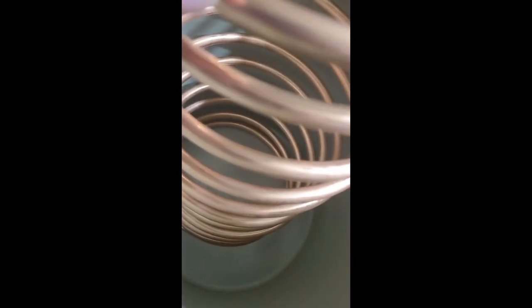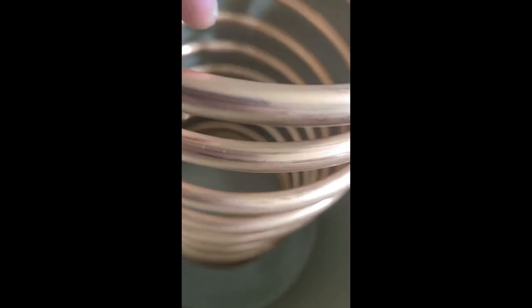Only thing is, with putting it that inch off the ground, it wants to not sit level and then your condensed vapor will pool back on the back side of your coil. It'll eventually build up and spurt out but not lead to a very good flow. So what we're going to do is pull it up and get that level.